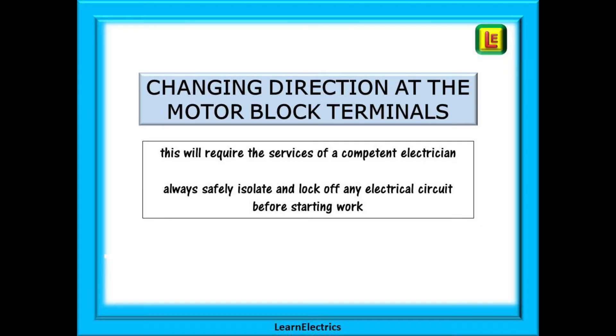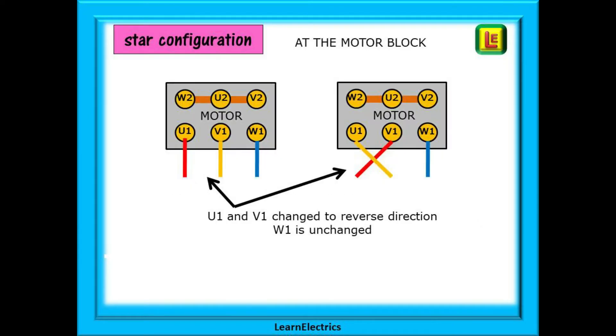So let's look at what is required. The links in the three-phase motor may be connected as a star configuration as is shown here. To change direction, leave the two links as they are and change any two of the incoming phase wires. Here we have decided to change the positions of the red and yellow wires.